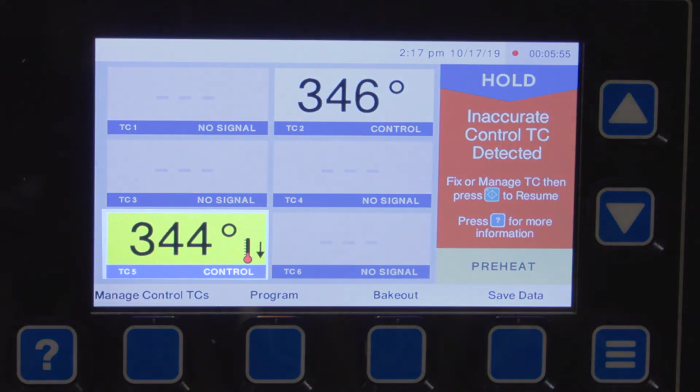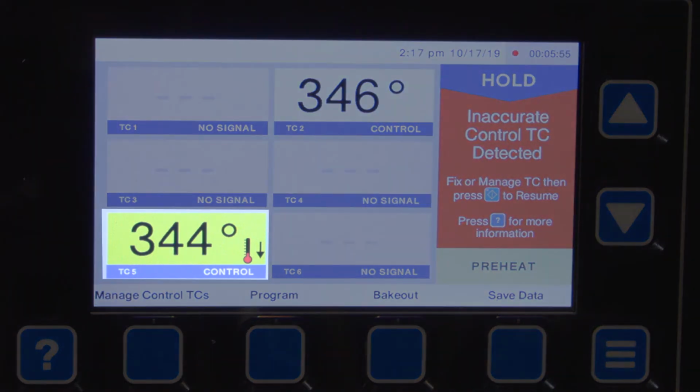This image depicts that the TC temperature is falling. If the part had been heating and a TC suddenly drops in temperature, the TC may have been pulled out from under the heating coil. The possible solution is to reposition or replace the TC.